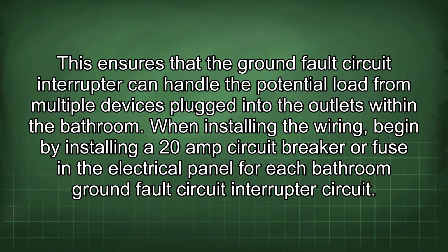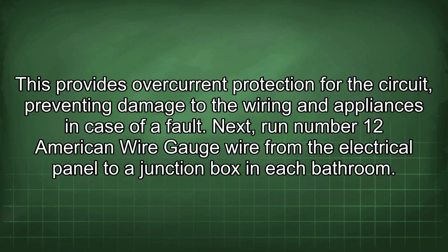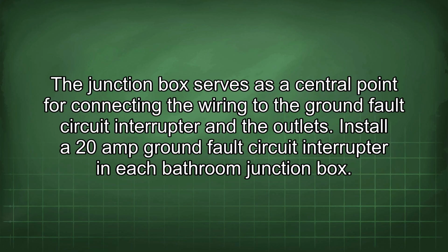When installing the wiring, begin by installing a 20 amp circuit breaker or fuse in the electrical panel for each bathroom ground fault circuit interrupter circuit. This provides overcurrent protection for the circuit, preventing damage to the wiring and appliances in case of a fault. Next, run number 12 American wire gauge wire from the electrical panel to a junction box in each bathroom. The junction box serves as a central point for connecting the wiring to the ground fault circuit interrupter and the outlets. Install a 20 amp ground fault circuit interrupter in each bathroom junction box.